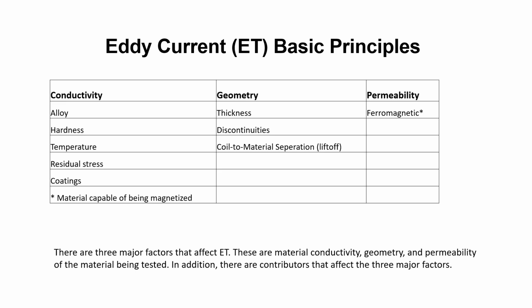There are three major factors that affect eddy current testing. These are material conductivity, geometry, and permeability of the material being tested. In addition, there are contributors that affect the three major factors. So we see here that conductivity can be affected by alloy, hardness, temperature, residual stress, and coatings. Geometry: thickness, discontinuities, coil to material separation. And then permeability: is it ferromagnetic? These are things that need to be taken into consideration by the eddy current testing technician.